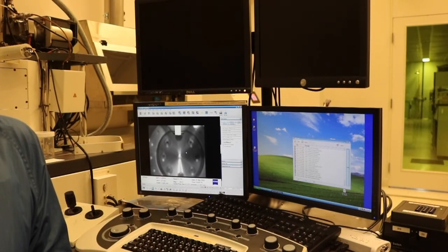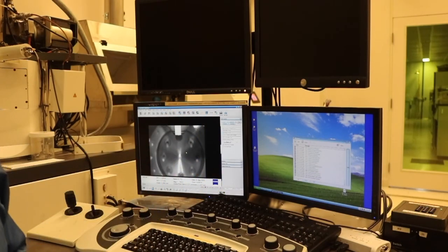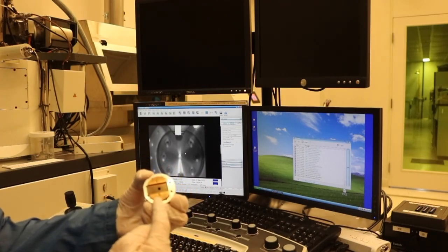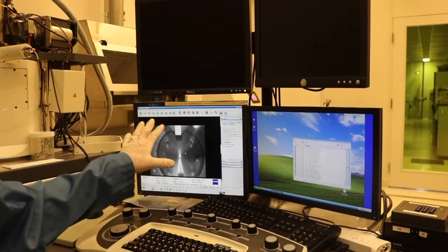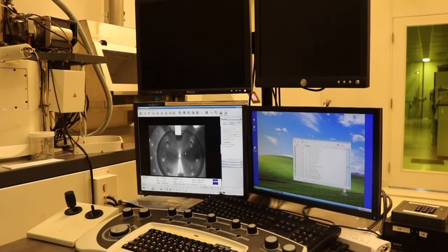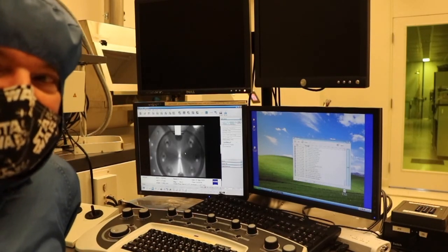The procedure that is done within this is detailed within the user training guide, and the reason that it is broken down into the individual steps is that should the exchange button not work, you can figure out how to do it. And again, remember that when you take the sample holder, you have a flat side and a round side. The flat side goes on first. There is no indicator as to when the vacuum will actually be ready for venting. Typically, the vent procedure takes about 3 to 4 minutes, and then the pump down procedure takes about an equal amount of time.